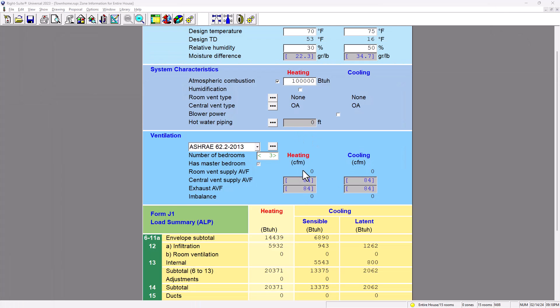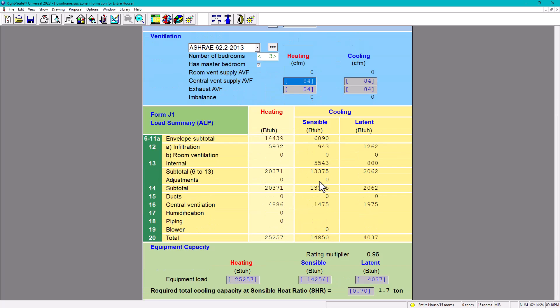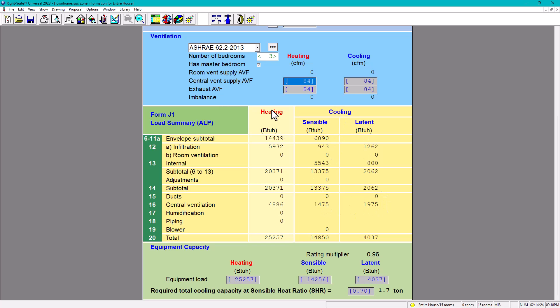So now we already established we need this ventilation, and in another video I'm going to be making this by hand - hand calculation. So the last part of this is, as you can see in here, you have room ventilation, infiltration, you have internal loads, and also you have in here number 16, that's central ventilation. So central ventilation for heating is this, for cooling is this, and latent is this. Why? Because in heating, if you are bringing outside air - imagine in heating, you are going to be very cold outside, like for example freezing. And if it's coming to your house, that's why you have a load. Or in summer, when you have like 100 degrees Fahrenheit outside, or in Celsius could be 40 maybe, you know, who knows. Then you're bringing inside hot air, and also humidity. So that's why you have this load, central ventilation.